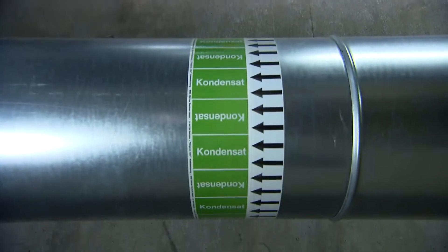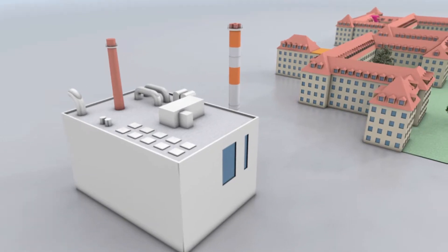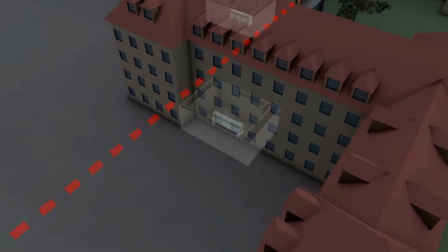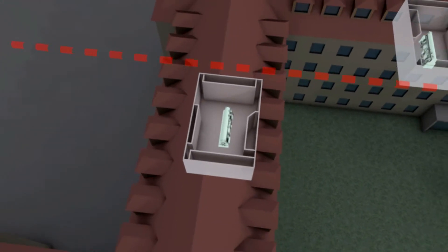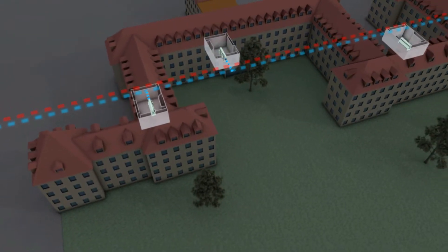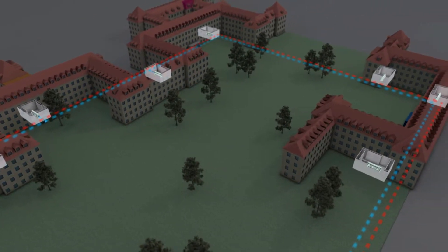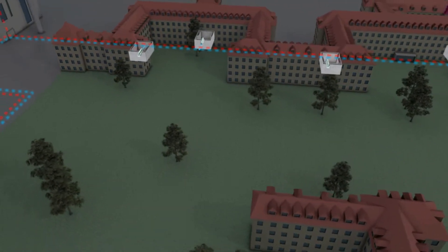There, the steam is used to sterilize and humidify the air conditioning system. In addition, the steam brings the hospital's heating system and sanitary water to the desired temperature. But the power plant's hot steam is also used to produce cold air. A physical chemical treatment turns the hot steam into cold air in eight so-called absorption refrigerators. Cold air from these special units is transported underground to the individual buildings in a so-called cold water ring. The advantage of this power grid is that the entire hospital's energy needs for heating and cooling can be efficiently produced by the COGAS power plant.